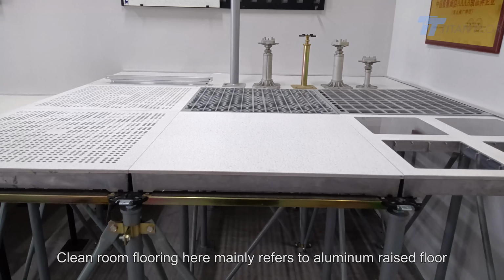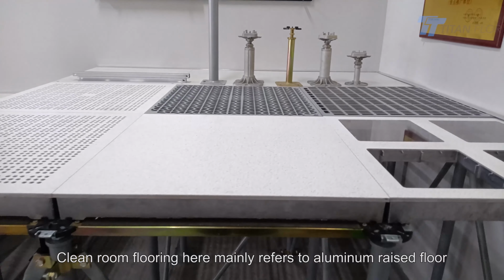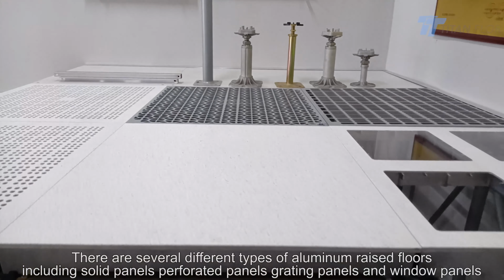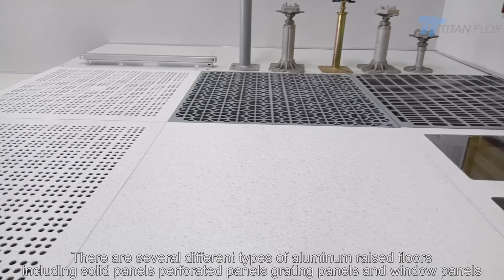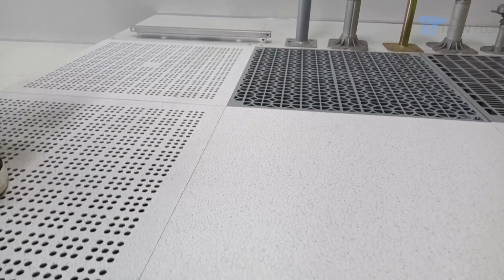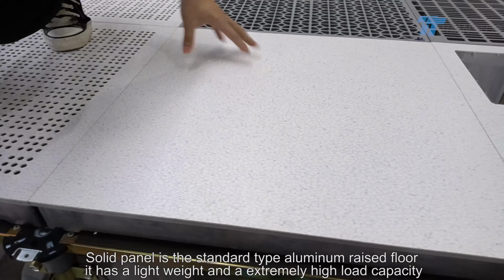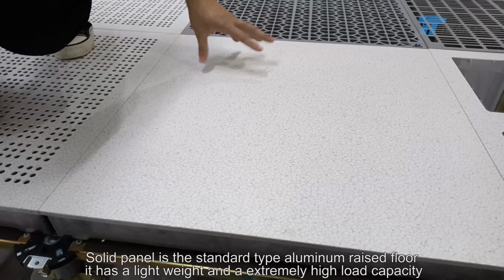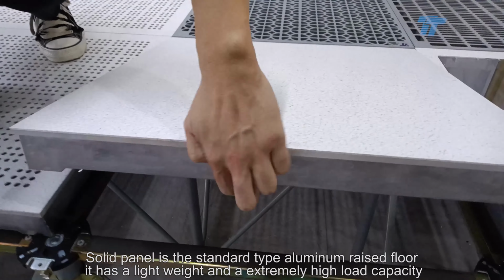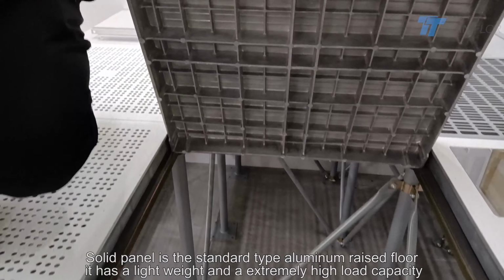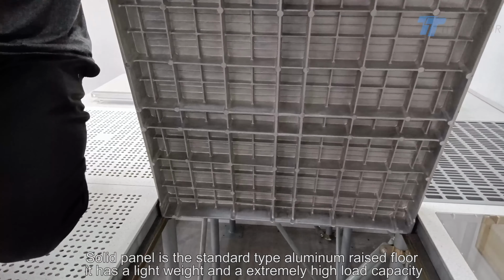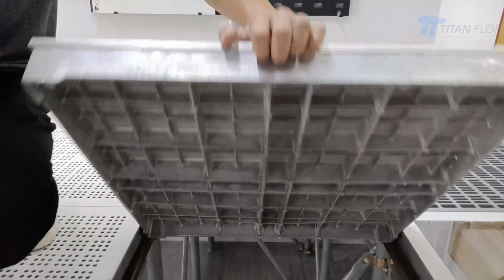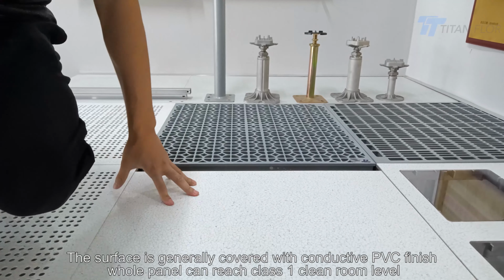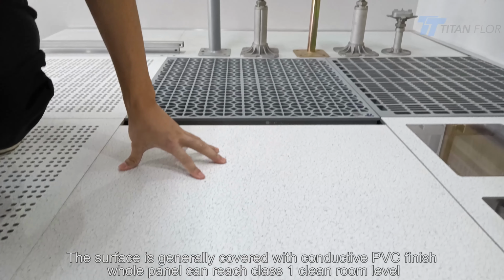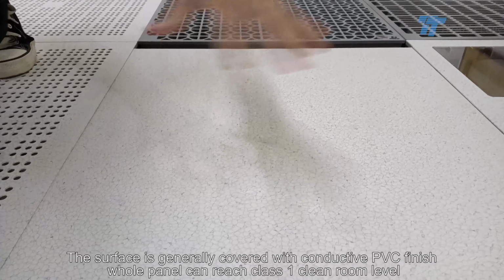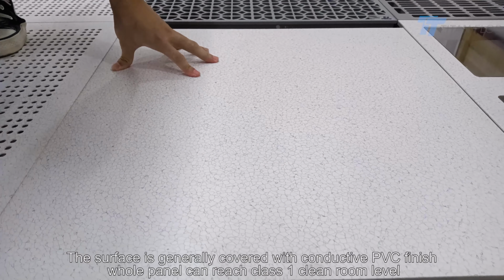Cleanroom flooring here mainly refers to aluminum raised floor. There are several different types of aluminum floor. This one is solid panel. It is a standard type of aluminum floor. It has light weight and extremely high load capacity. The surface is generally covered with conductive PVC finish. The whole panel can reach Class 1 cleanroom level.